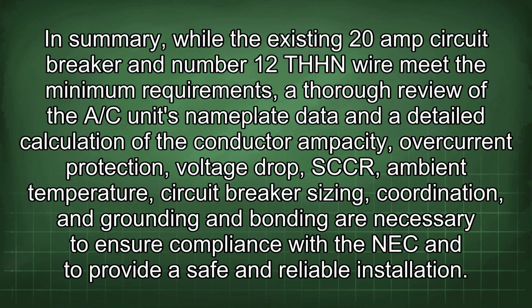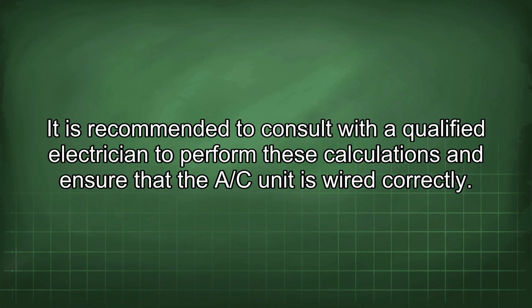In summary, while the existing 20 amp circuit breaker and number 12 THHN wire meet the minimum requirements, a thorough review of the A/C unit's nameplate data and a detailed calculation of the conductor ampacity, overcurrent protection, voltage drop, SCCR, ambient temperature, circuit breaker sizing, coordination, and grounding and bonding are necessary to ensure compliance with the NEC and to provide a safe and reliable installation. It is recommended to consult with a qualified electrician to perform these calculations and ensure that the A/C unit is wired correctly.